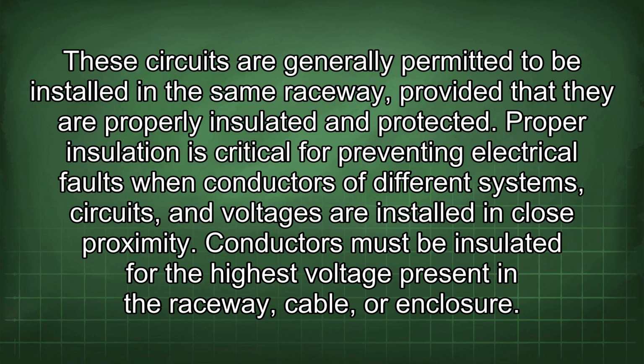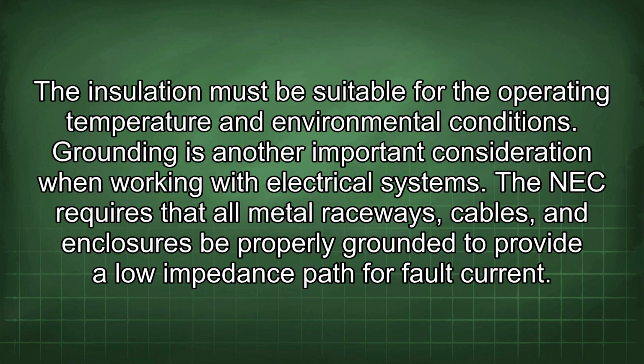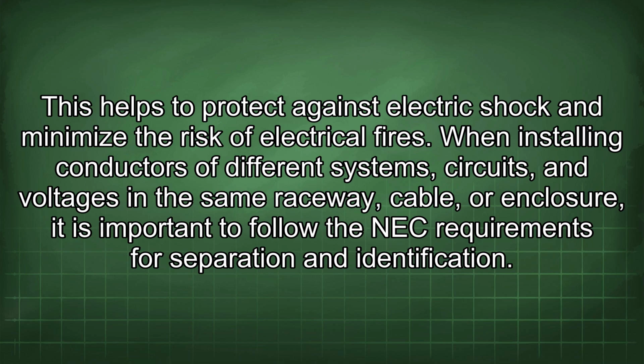Proper insulation is critical for preventing electrical faults when conductors of different systems, circuits, and voltages are installed in close proximity. Conductors must be insulated for the highest voltage present in the raceway, cable, or enclosure. The insulation must be suitable for the operating temperature and environmental conditions. Grounding is another important consideration when working with electrical systems. The NEC requires that all metal raceways, cables, and enclosures be properly grounded to provide a low impedance path for fault current. This helps to protect against electric shock and minimize the risk of electrical fires.